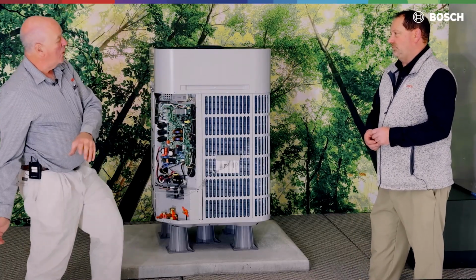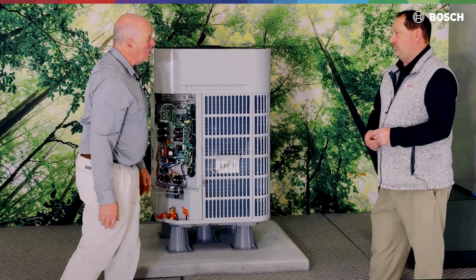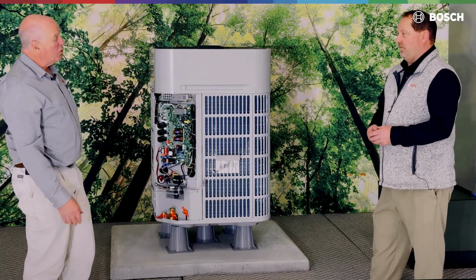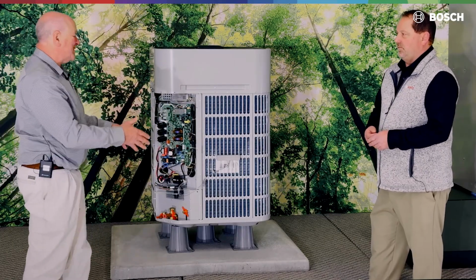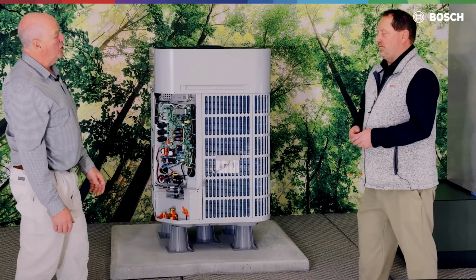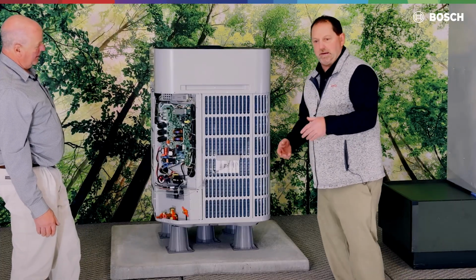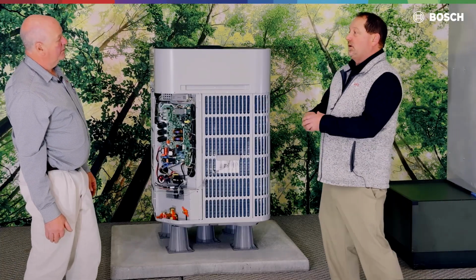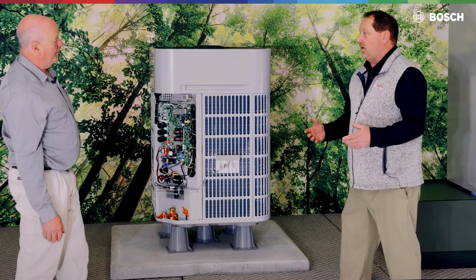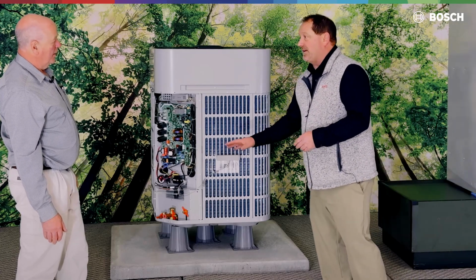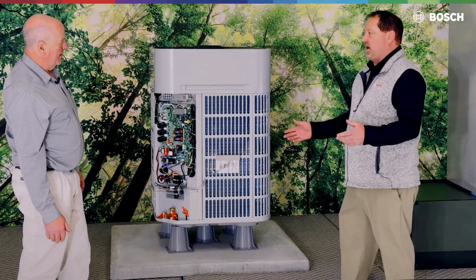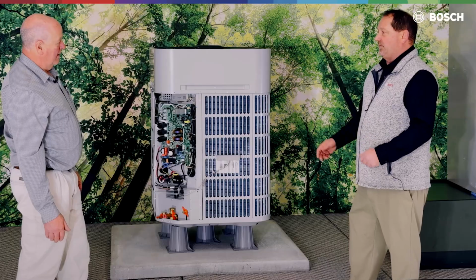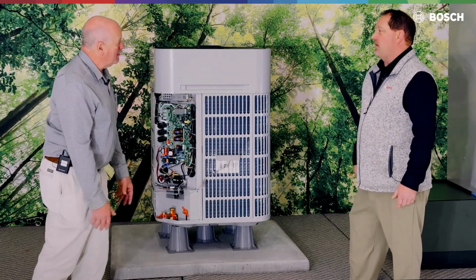While we're doing that, we can go inside and hook on ductwork, hook up thermostat wiring. So we're always being productive with our time. We're not sitting there watching a vacuum pump do its mission. So in the event that I am in a high moisture type climate in that particular part of the year, I'm going to go triple evac. If I'm not in that particular moisture type environment, deep vacuum's plenty adequate. Yeah, I like the triple vac personally, but that's up to your call.